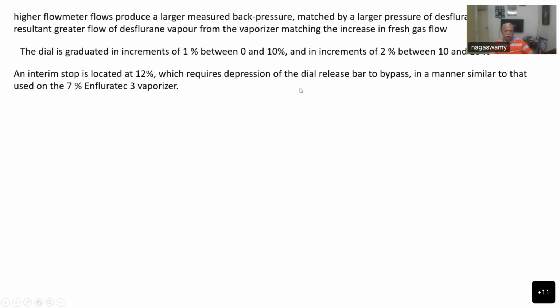So whatever fresh gas flow you alter, the vapor pressure from the desflurane tube side will equally match to maintain the same concentration. And the dial is graduated in increments of 1% between 0 and 10 and increments of 2% between 10 and 18. But at 12%, there is a need to depress. That is one of the safety features.